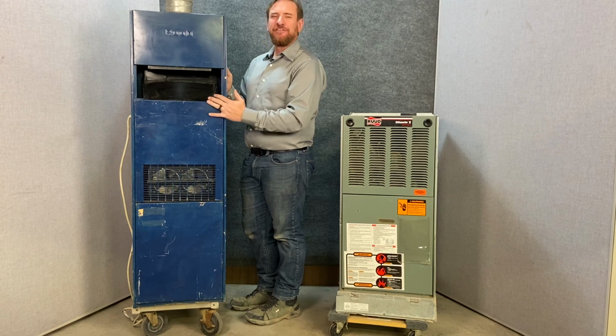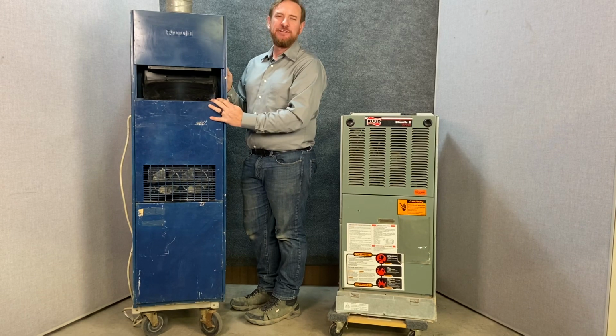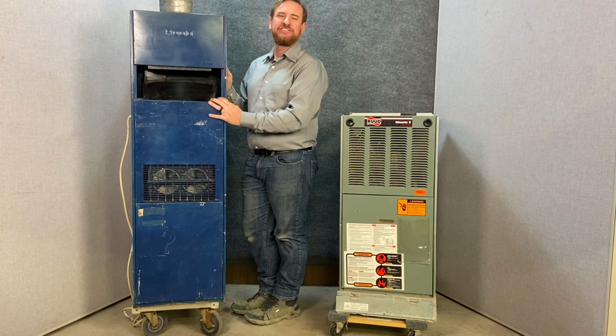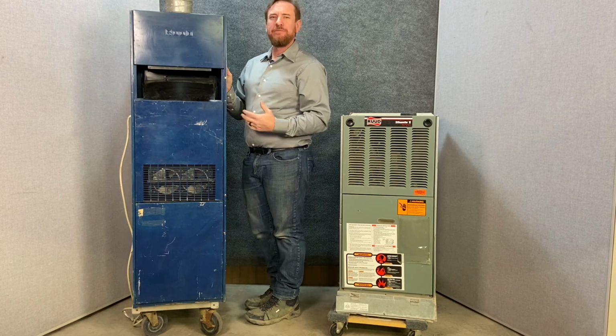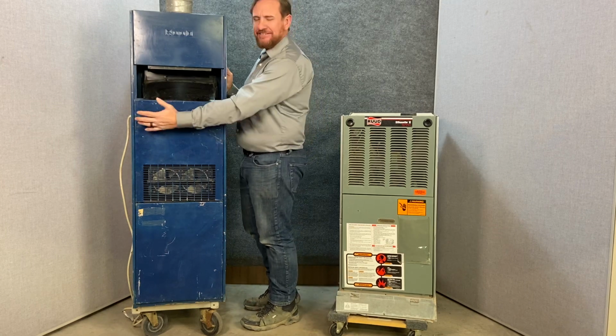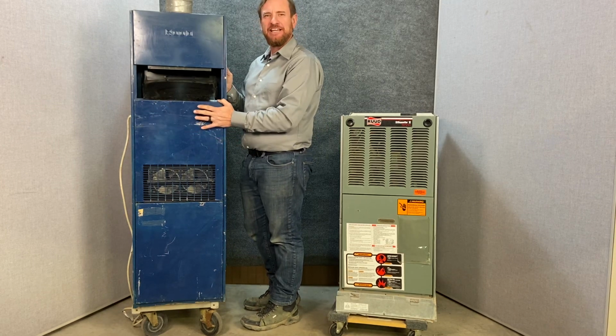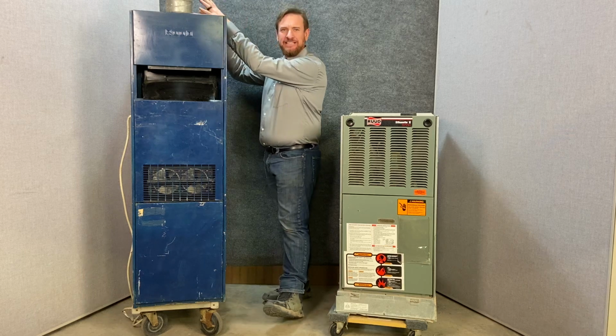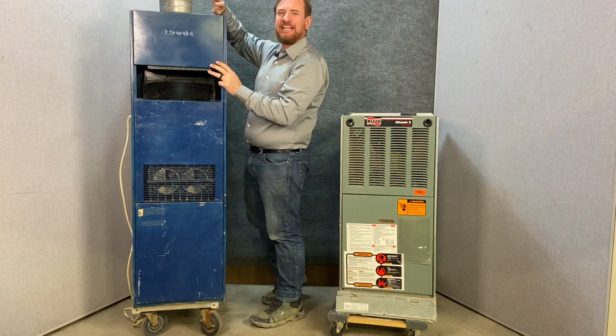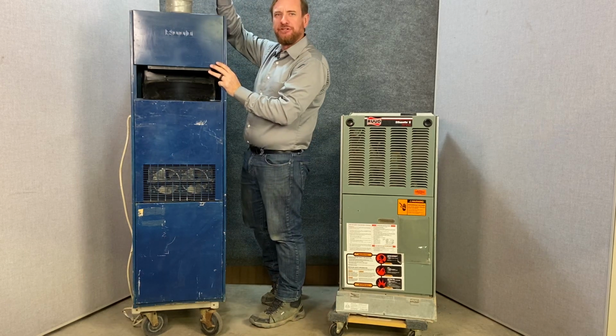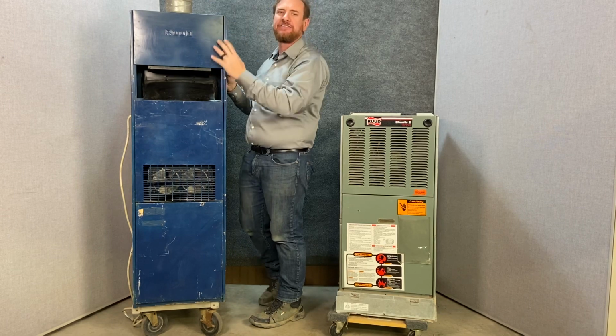This furnace is a 60% AFUE furnace. Now, that abbreviation stands for Annual Fuel Utilization Efficiency. So what that really means is this furnace, of the natural gas that I'm buying, it's converting 60% of that natural gas into the heat that's going in to heat your house. 40% of that gas is just going out the flue pipe. So you're losing 40% of that just straight outside.